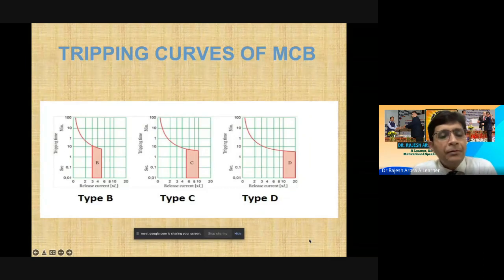For your B type MCB, usually the operating time is 5 times the rated current. For C type, it is 10 times, and for D type, it is 20 times. Based on your requirement, kindly choose your MCB and look at the tripping curve.